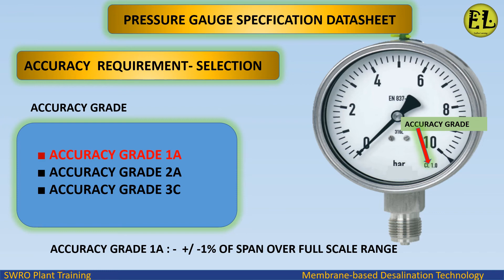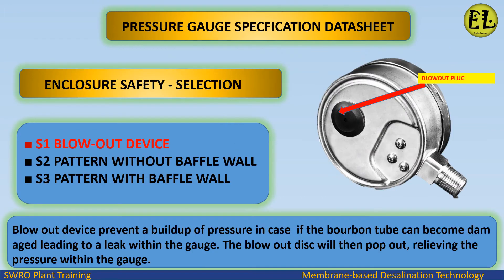Enclosure safety selection. Options are S1 blowout device, S2 pattern without baffle wall, and S3 pattern with baffle wall. The blowout device prevents a buildup of pressure in case the Bourdon tube becomes damaged and leaks within the gauge — the blowout disc will then pop out, relieving the pressure. We select the blowout device for this application.